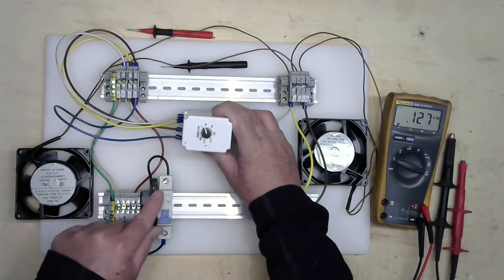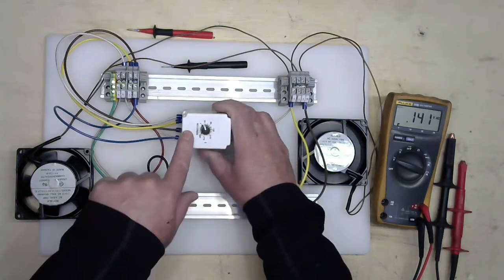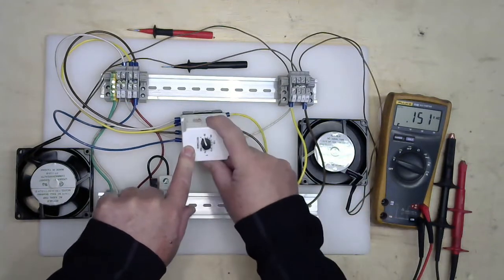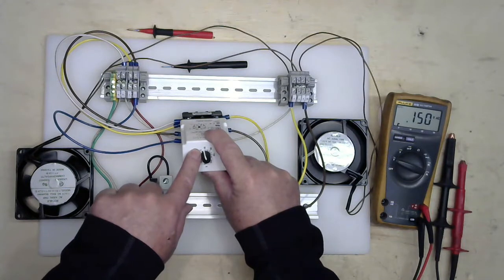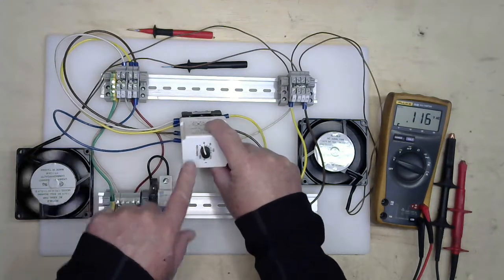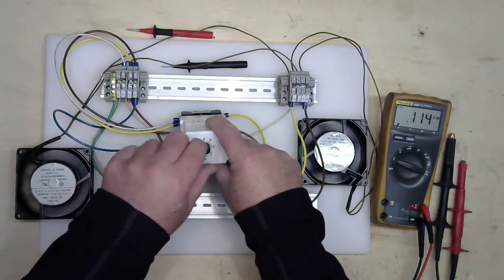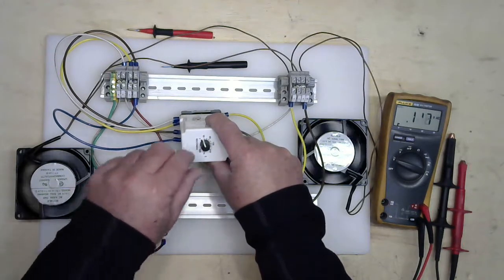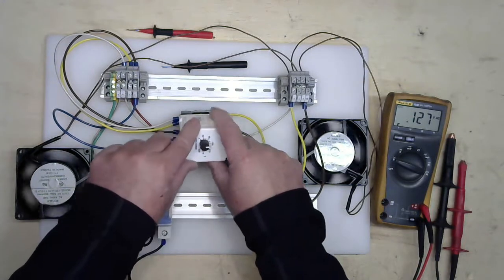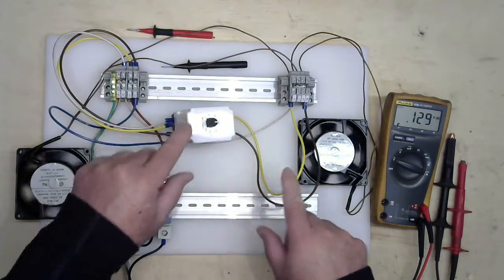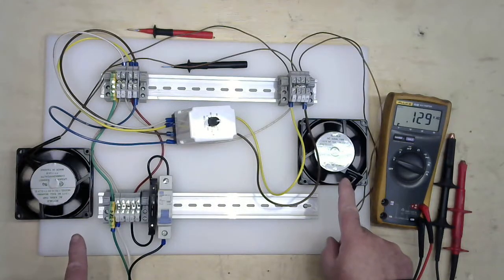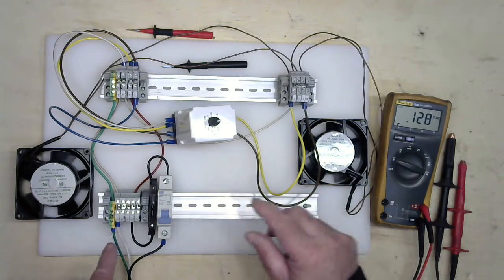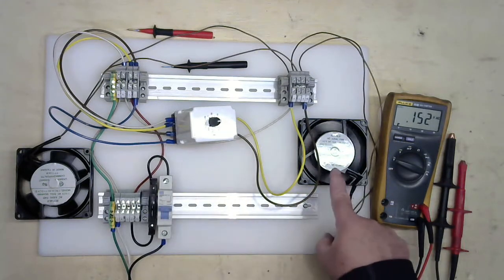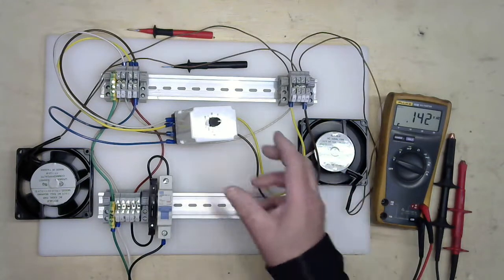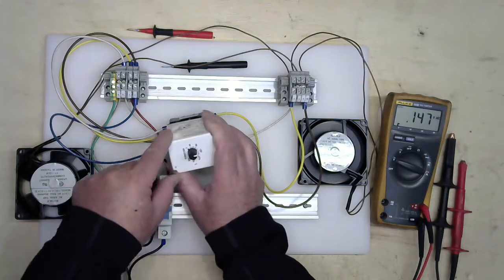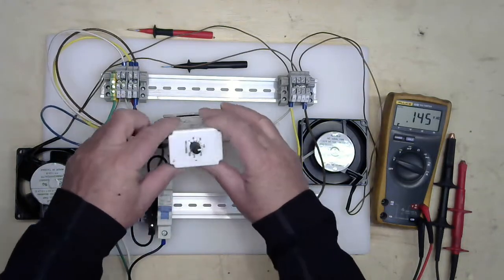See my timer. Apply power. My fan here is now operating. It's going to time out in roughly 15, 18 seconds here, according to my timer. Once you apply power, I'm going to go ahead and increase my timing to 150 seconds. Wait for both fans to stop spinning. Apply power once again. My normally closed terminal is turning on my fan, but now I have already set 150 seconds.